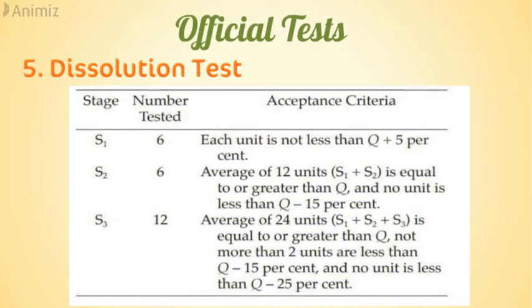The acceptance criteria for the dissolution test work in three stages. In Stage 1, 6 tablets are tested and each unit must be not less than Q+5%, where Q is the specified percentage of drug dissolved. If that fails, Stage 2 tests 6 additional tablets: the average of 12 must be ≥Q and no unit less than Q−15%. If Stage 2 also fails, 12 more tablets are tested: the average of 24 units must be ≥Q, not more than 2 units may be less than Q−15%, and no unit shall be less than Q−25%.